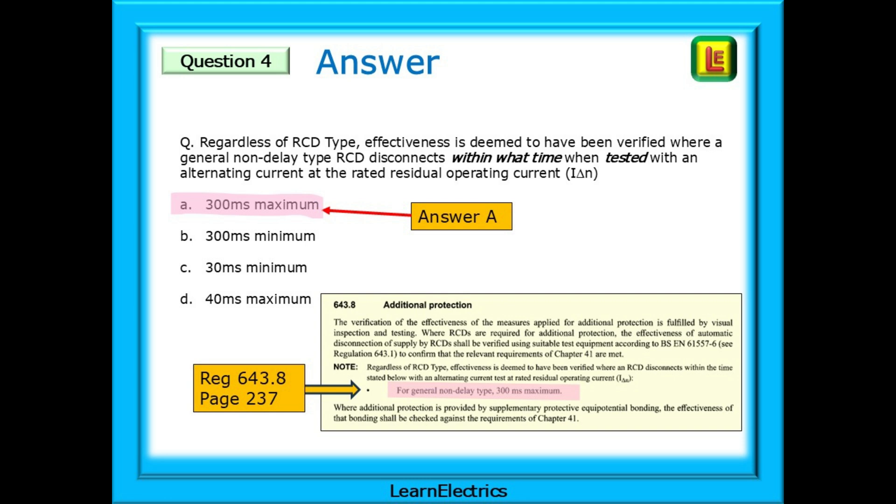The clue is the word tested, that should take you to part 6 of the book, Testing. After that, finding 643.8 is easy. This is the only RCD tripping test that we are required to do now, regardless of type AC, type A, type B, or type F. No need for 5 times test if you don't need to do it. Many, though, still do.